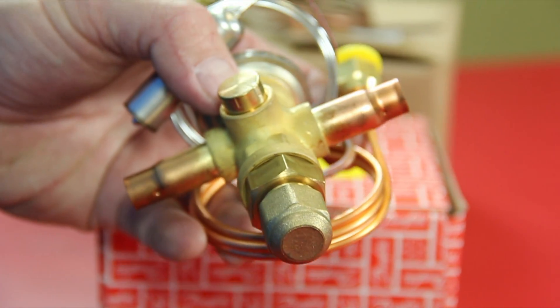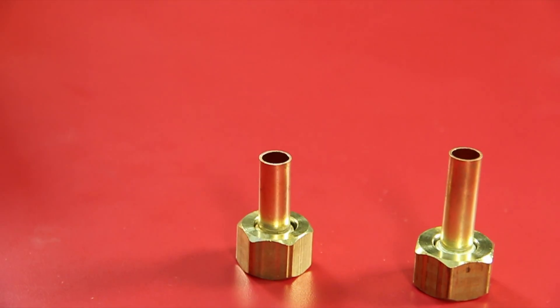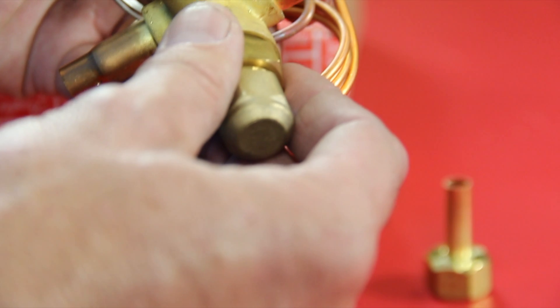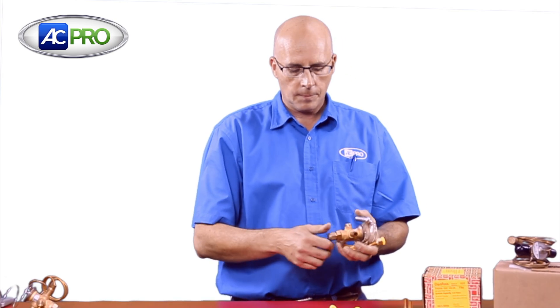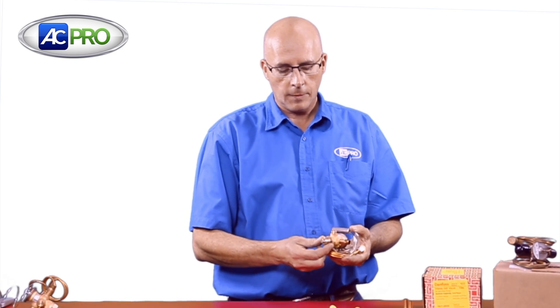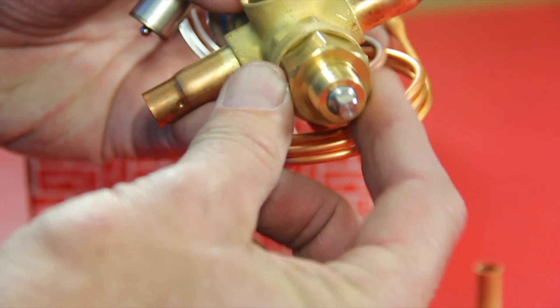It comes with no fittings attached, so there's a little more work to install, but you have more options. It comes with flare and sweat fittings, which gives you more versatility, making it a good universal valve. It has an adjustment here at the base for the superheat, which will help you dial that in.